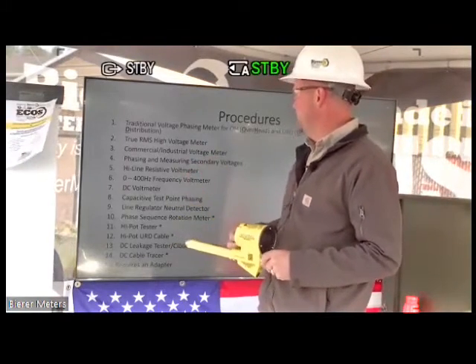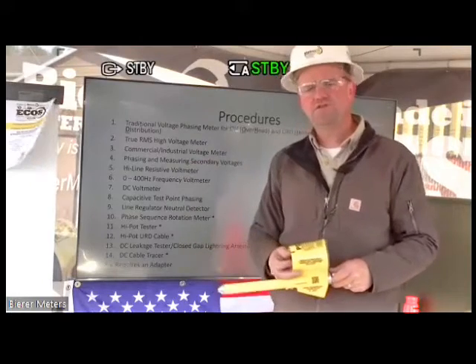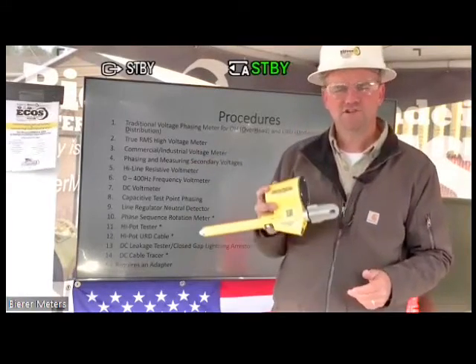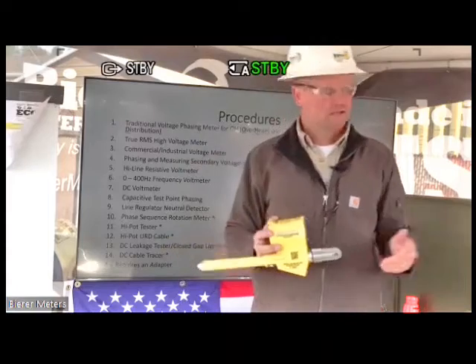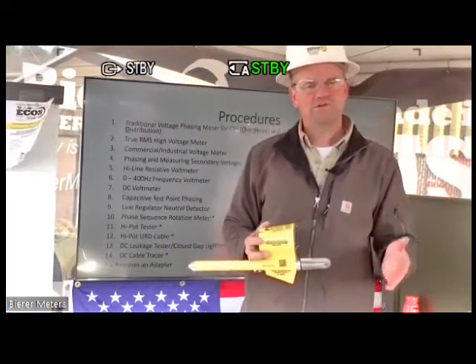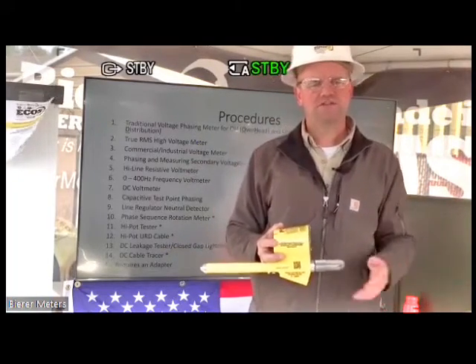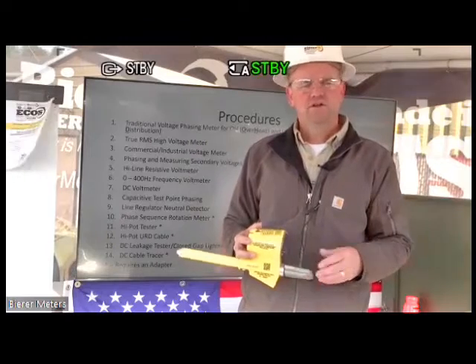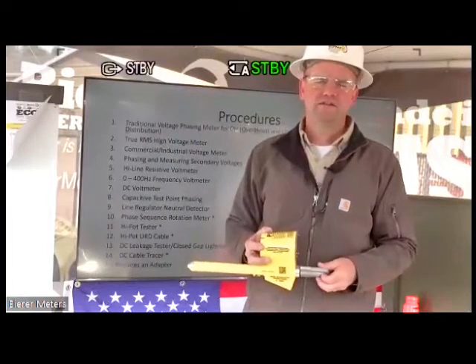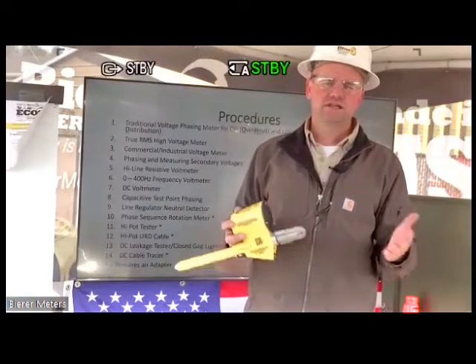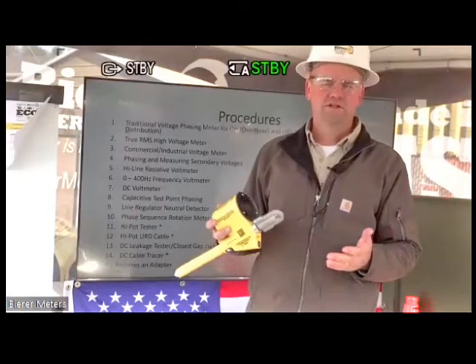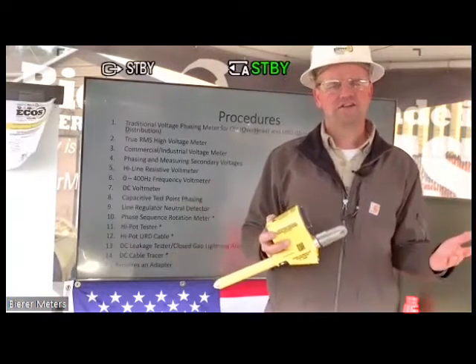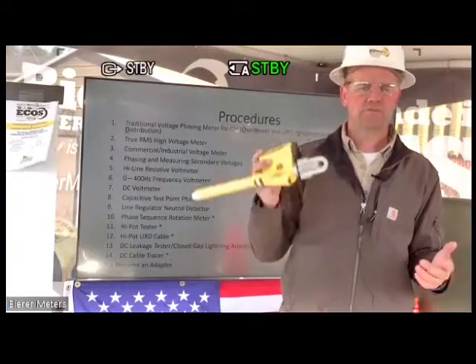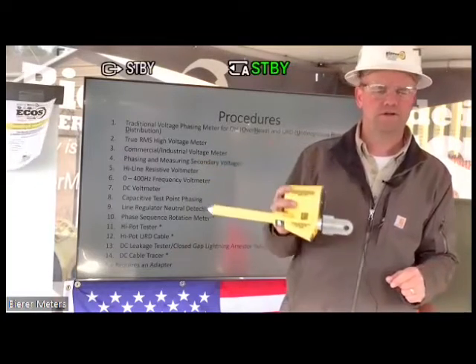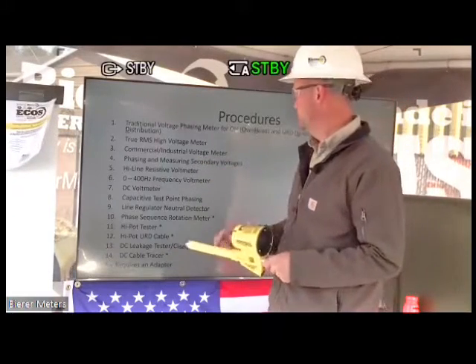A phasing meter, for measuring secondary voltages. Again, since it is a true RMS meter, I can use it on 120 to 208, which we'll demonstrate here. We have some 3-phase here in our training yard. Your 277/480, your 600 volts, any type of potentials where, again, traditionally that phasing meter could not handle that. The PD25 has no problem accomplishing that task.